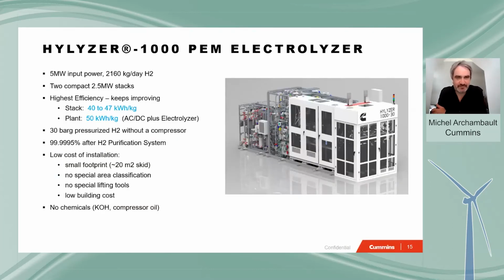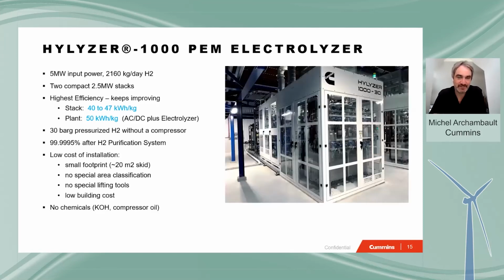That product, producing 2.1 tons per day, uses 2 stacks. It has an efficiency of 40 to 47 kilowatt hours per kilogram, but 50 kilowatt hours per kilogram at the plant level, which includes rectification of power from AC to DC with a transformer. We're taking medium voltage, anywhere between 4.16 kilovolts to 35 kilovolts.